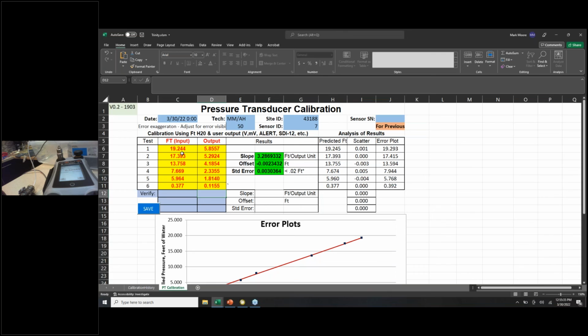What we're actually finding is that across the range of this PT, it's accurate to 0.003. It's almost 10 times better than the specs say. So it's accurate to within 0.003 of a foot, up to 20 feet deep. That's good. I mean, that's as good as a PT is going to get. And this is a new one. It's off the shelf. It's not been in the field, so we really should see it be low. But that's still great to see.